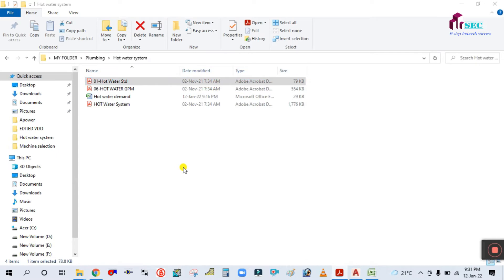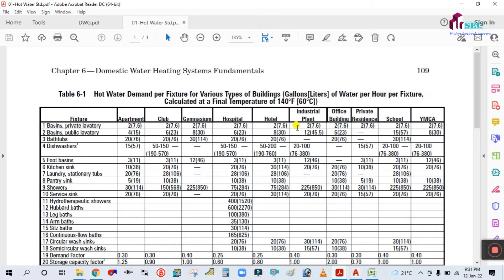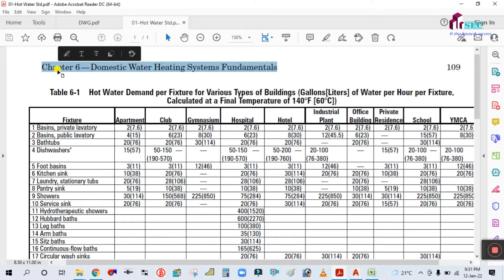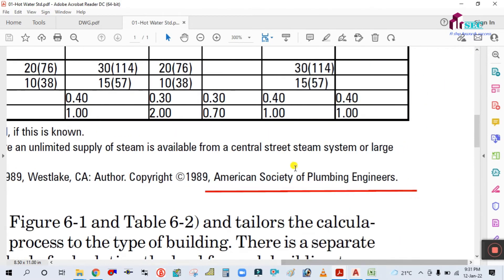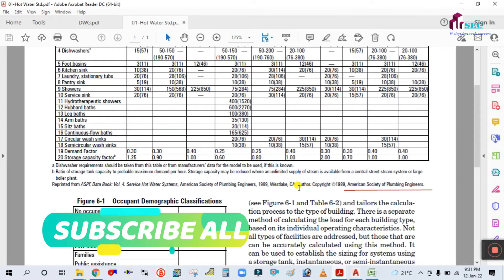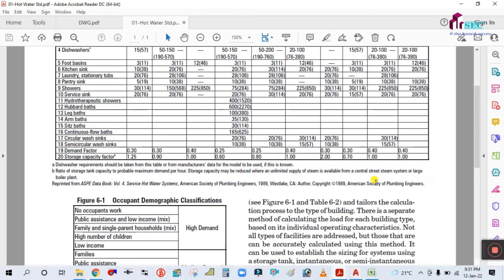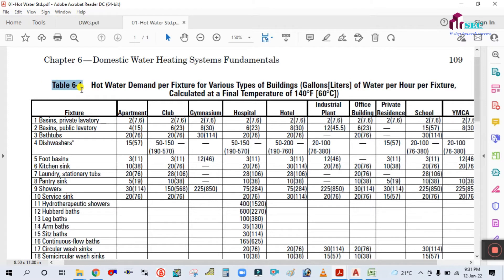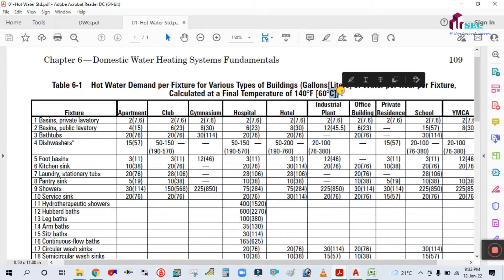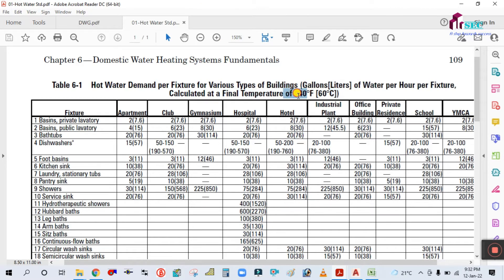For the GPH value, let us open this standard. You can see this is the Domestic Water Heating System Fundamentals, Chapter 6, taken from the American Society of Plumbing Engineers (ASPE). If you see here, Table 6-1 shows hot water demand per fixture for various types of buildings — gallons and liters of water per hour per fixture, calculated at a final temperature of 140°F (60°C).